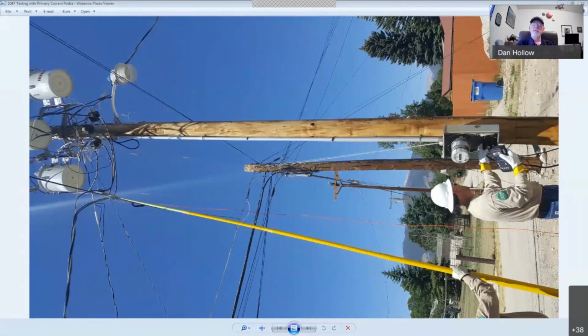So you would put that fork type probe on the conductor exiting that first CT on the bracket and find that that wasn't phase A. It may have been B, it may have been C, but the way to find that is to keep moving that duckbill connector on the secondary of the transformer, moving it from one test jack to the next until you find the secondary current that makes sense. If it's not the right CT that you have that high voltage probe on, you'll just get a jumping number. It won't be stable. Once you find the proper conductor, you'll see a nice secondary that matches the ratio. You'll get the primary and secondary current that are relevant, whether it's 40 to 1 or 80 to 1 or whatever the case may be based on that CT ratio. You'll see something that makes sense.